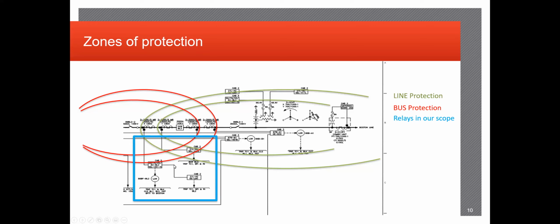Anything else that may be associated with the protection could still be included, such as these backup relays over here and the lockouts. However, in this application, we're primarily focused on replacing and upgrading this equipment. But when you do go through your isolation procedures, you do want to identify any possible equipment that may be involved in the string of circuits that you're going to be working on. Again, this identifying the 86 lockout relay that would be associated with this equipment alongside probably much more equipment.